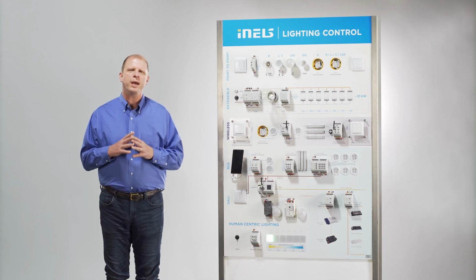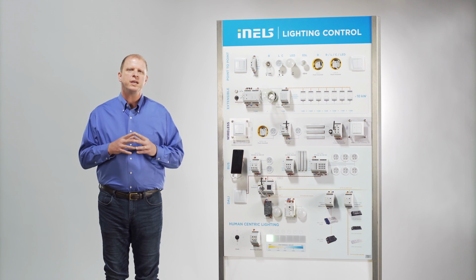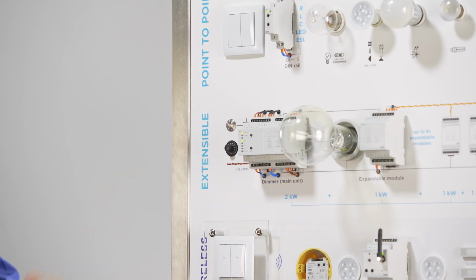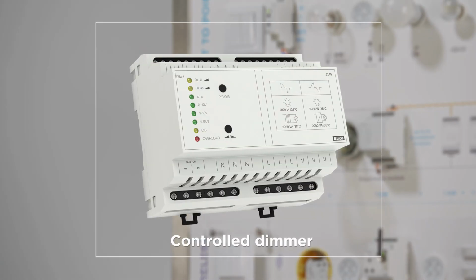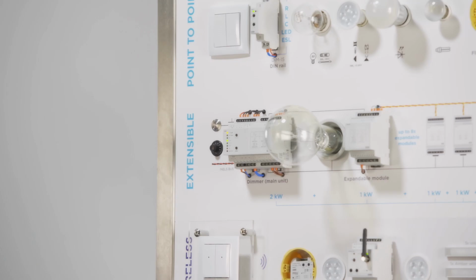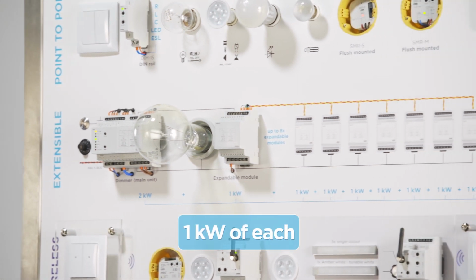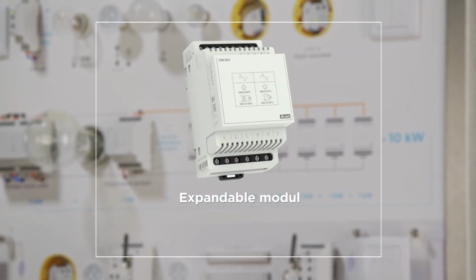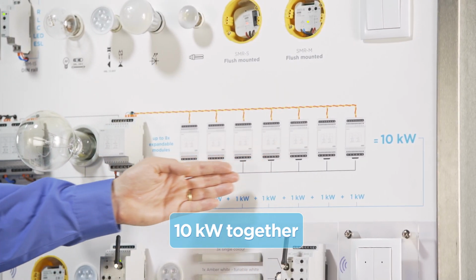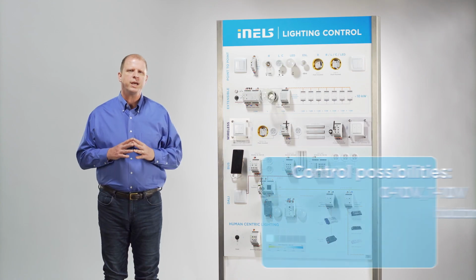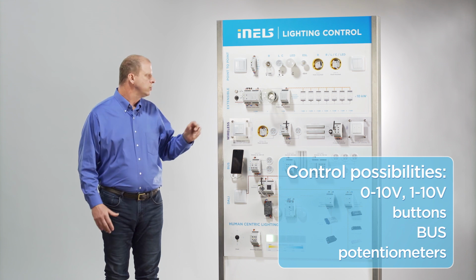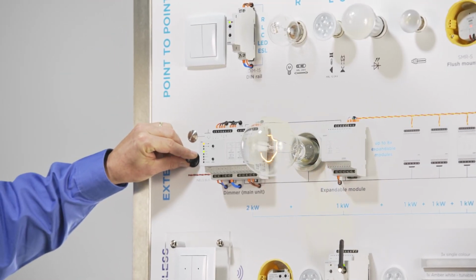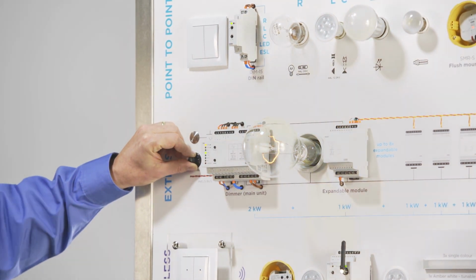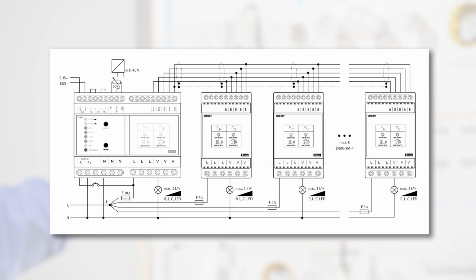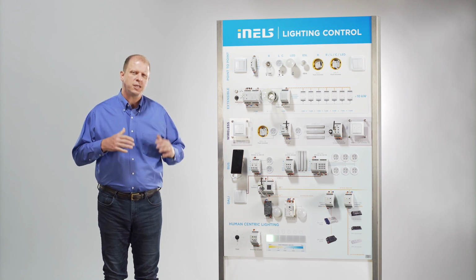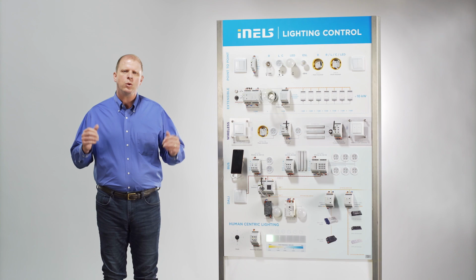Our solution is also able to cover the control of high loads using a dimmer DIM6 capable of controlling up to a 2 kilowatt load. It can be extended with additional modules capable of dimming loads of up to 1 kilowatt. Such a configuration can control up to a 10 kilowatt load. Dimmers can be controlled in various ways, like 0 or 1 to 10 volts DC. It is suitable for demanding operations, such as shopping centers, industrial halls, or warehouses.